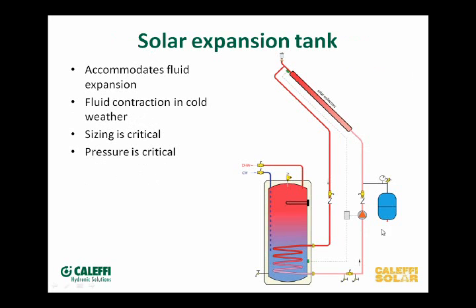Now we're at the expansion tank. We've been taught from the hydronic side — from Holohan, Gil Carlson, and others — that you always want to pump away from the expansion tank, the point of no pressure change in the system. So the tie-in should go before the pump. There's a quandary here: we'll explain when we get to our pump station why the pump is on the other side — and we've been called on that a couple of times. The sizing of a solar expansion tank is quite different than a hydronic expansion tank.